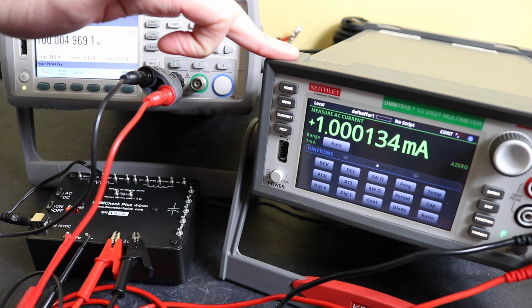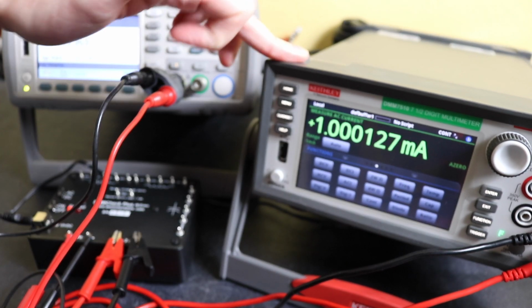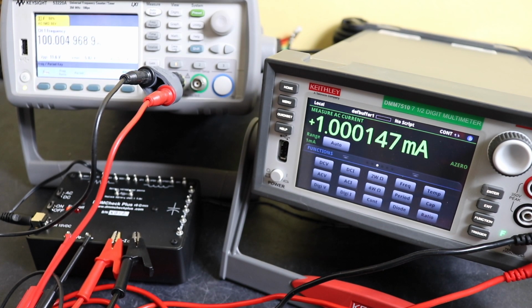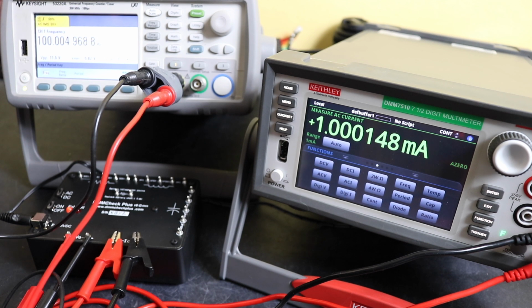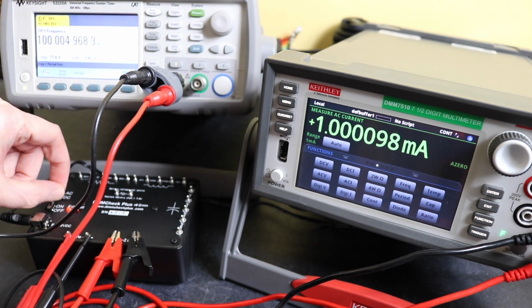I've now switched this one off, repowered it all back up, let everything settle again, reset all of this one, and we are now reading 1.0001 milliamps, which is a much better value, and we are at 100 hertz on the frequency counter.